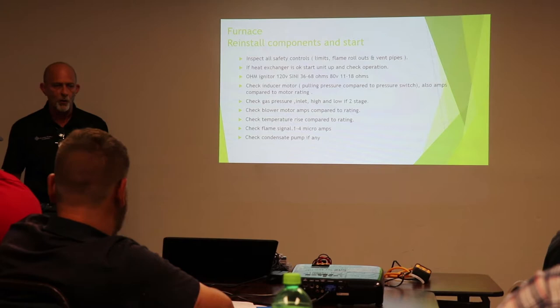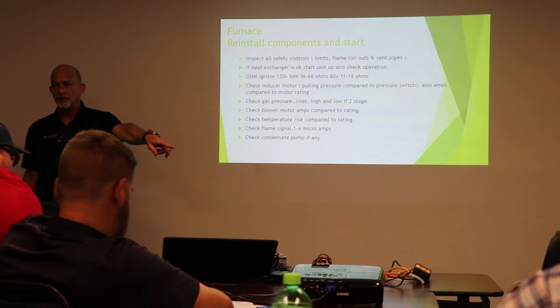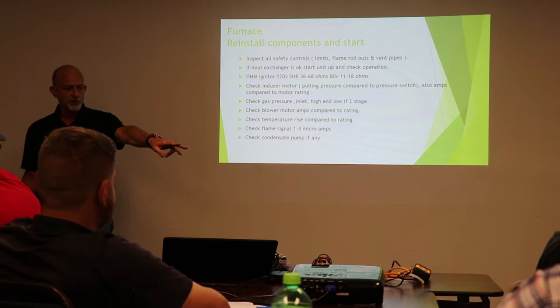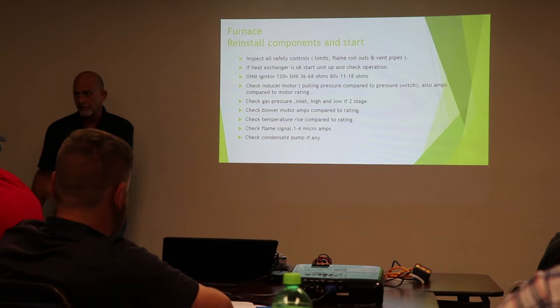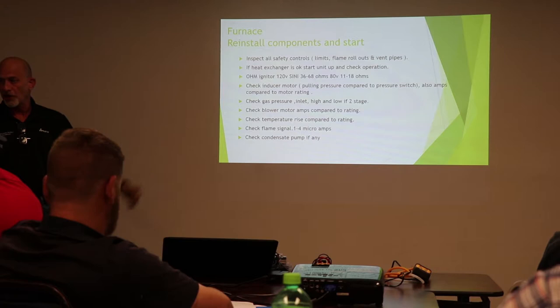With that one, you can monitor inlet and manifold at the same time. It'll read separately, P1, P2. So you can use it to monitor two hoses, one on inlet, one on manifold. Check our blower motor. Compare it to the rating of the motor. Make sure we're running at proper amps. After we get done, we're also checking our temperature rise. That's normal. Everybody in classes I've done, always raise your hand. I always check temperature rise.